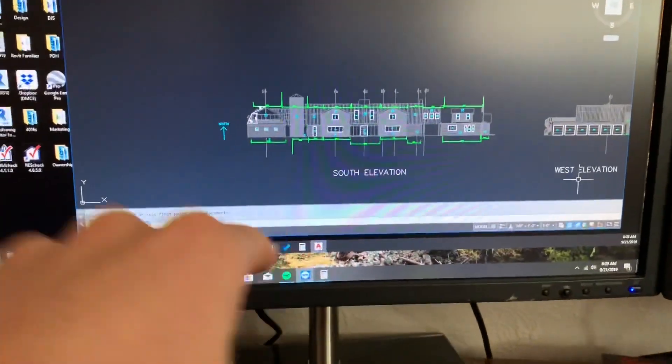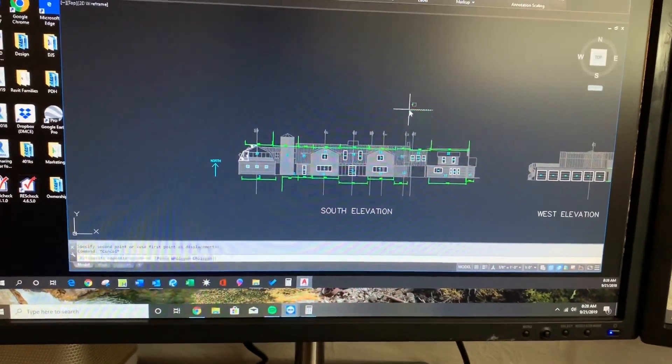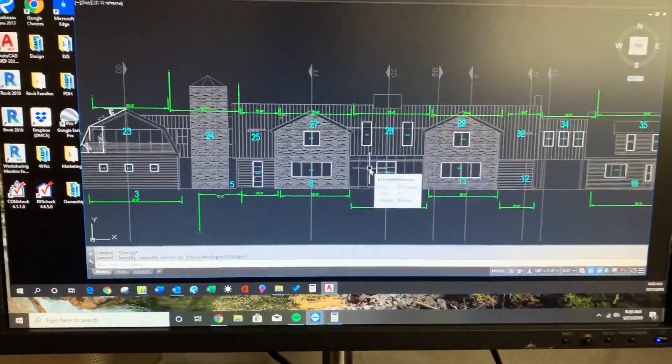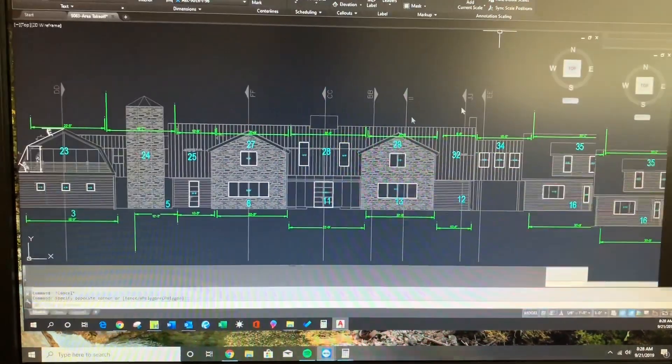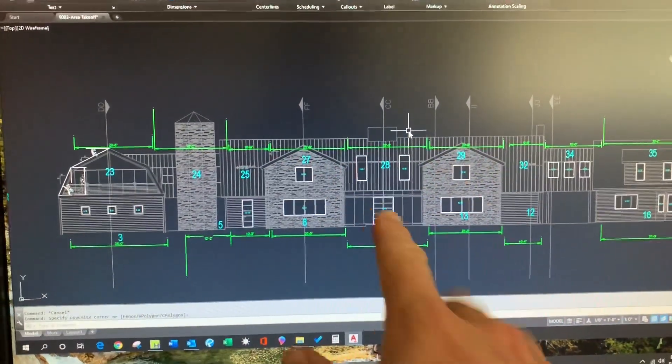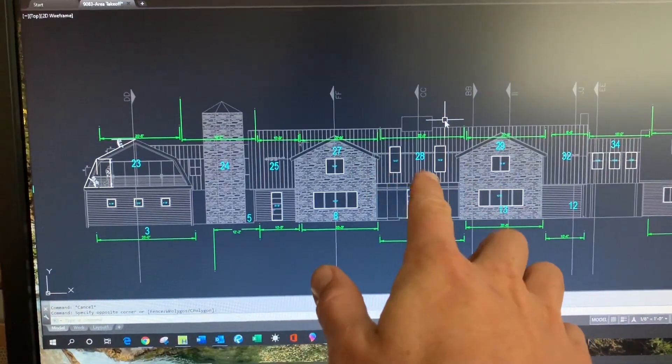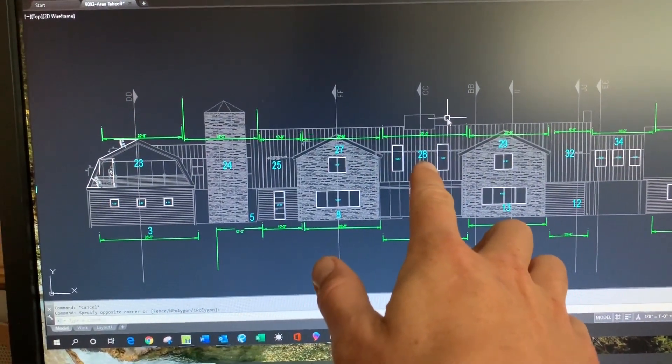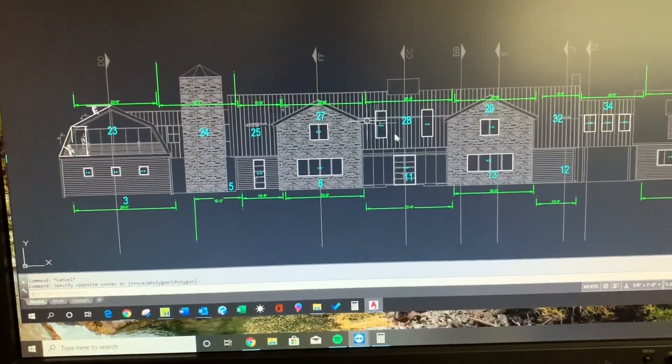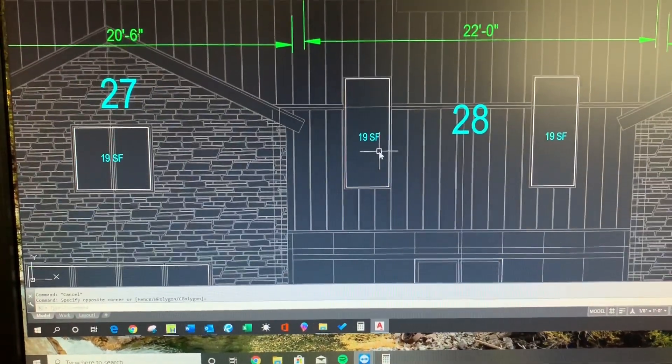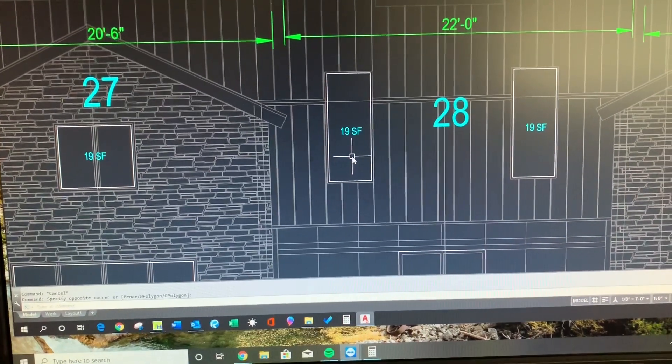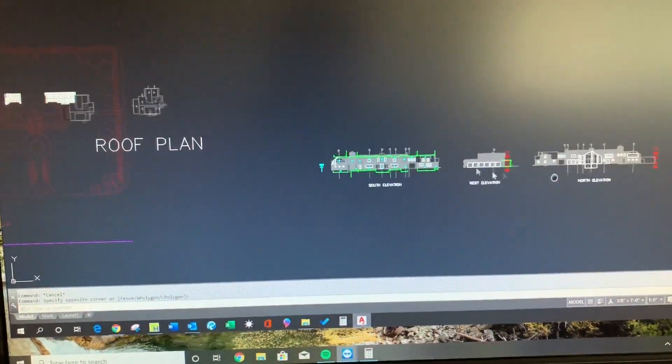All right so what I've been doing, I'm looking at the elevation profile of this large house and I want to make sure I'm accounting for all the windows on each face of the building. These are the rooms, the perimeter exterior lengths of the rooms. These are the zone room numbers that are going into the load calculations. You go in and you find all glass surface. Each one of these windows are 19 square feet. So I'm going to take all that. That's just the south elevation of the house.